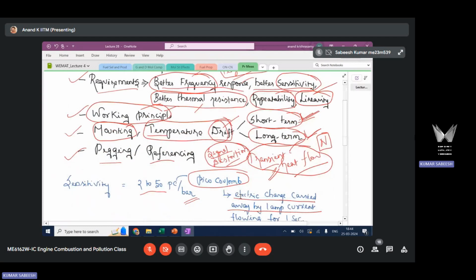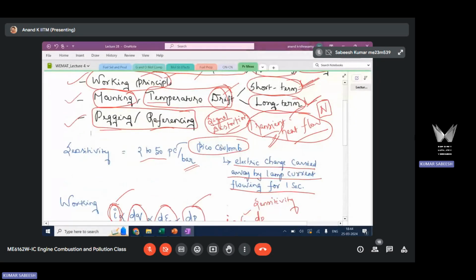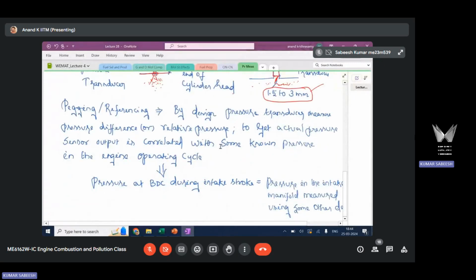The last point is about pegging or referencing. In principle, whatever sensor output you get is a pressure difference. In order to get the actual pressure value, by design, as I said, this I is related to dP by dt, not P. It is dP. So by design, this is how the sensor is designed. The transducer measures the pressure difference, not the absolute value of pressure. It is a difference or relative pressure.